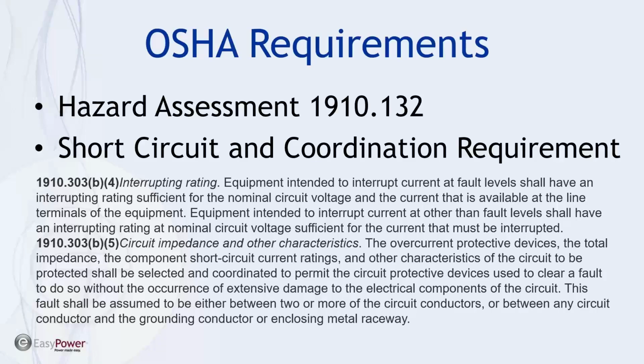So if it's an arc flash hazard that you're assessing, somehow you have to assess what that is. You can go by tables in NFPA 70E, or you go by labels from an engineering study. An engineering study is going to be a lot more accurate and give you a lot more detail, and it does the short circuit and coordination study requirement. So let's take a look at that.